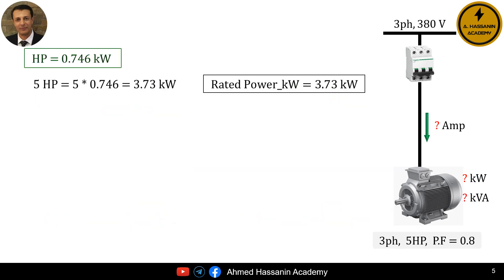If the rated power of the motor is given in HP, we can convert this value to KW using the equation: one horsepower equals 0.746 KW. Therefore, for 5 horsepower: 5 HP equals 5 multiplied by 0.746, which means 5 horsepower equals 3.73 kilowatts. Thus, the rated power of the motor is 3.73 kilowatts.